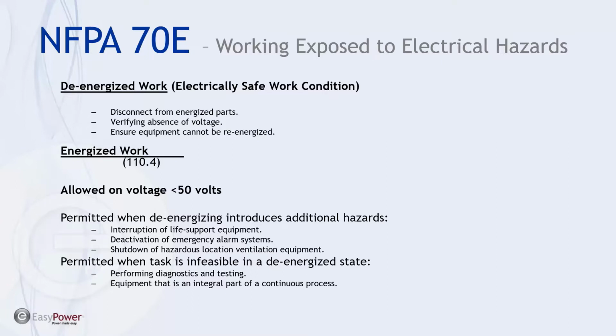The second is when de-energizing the equipment introduces additional hazards, which you would expect to see maybe in medical equipment where there's life support equipment, or emergency alarm systems, or equipment that needs to be up 100% of the time. And then finally, when the permitted task is infeasible in a de-energized state.